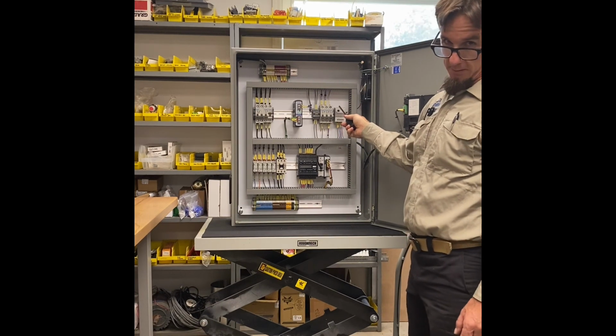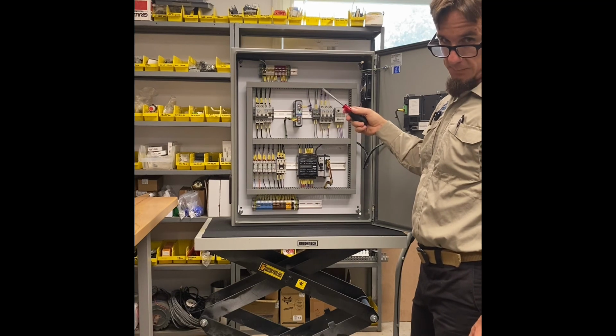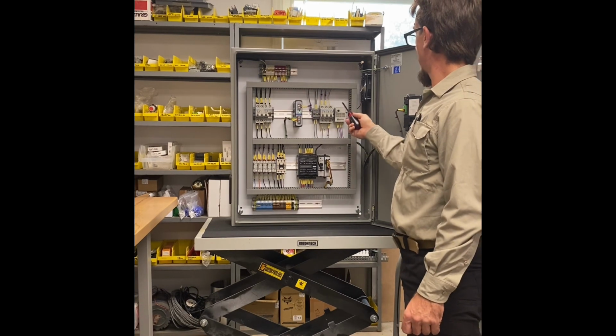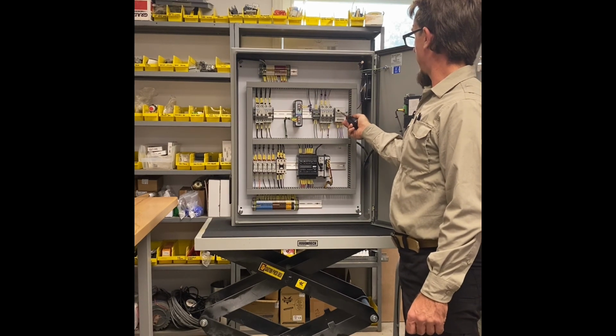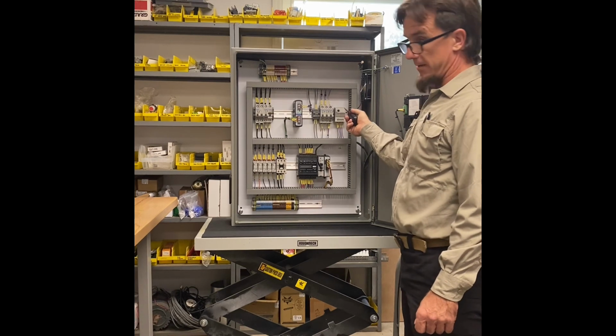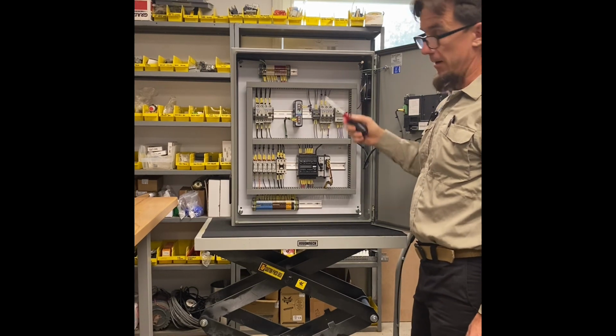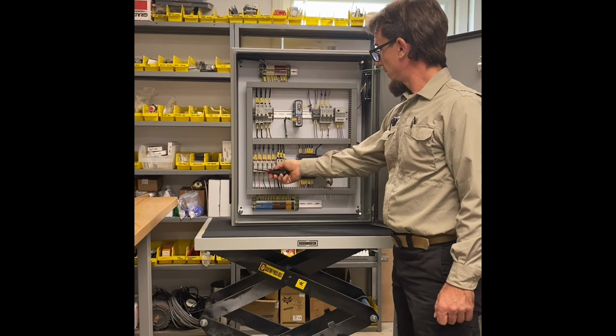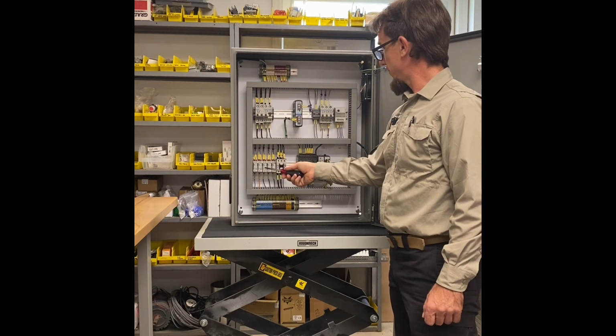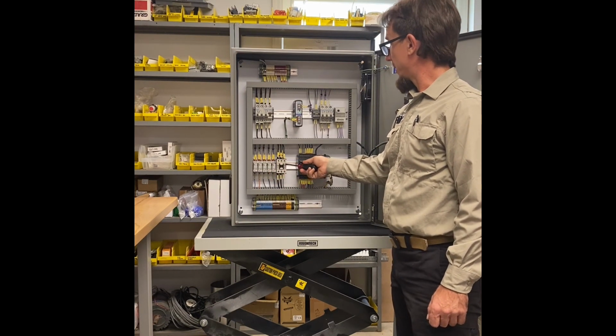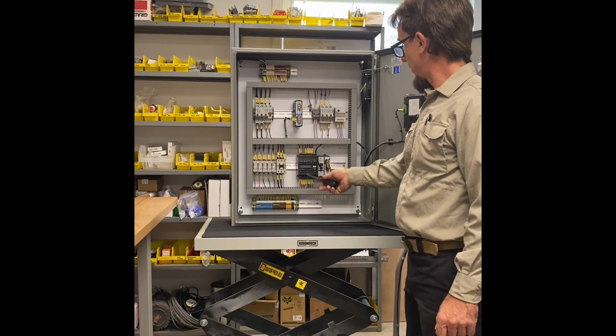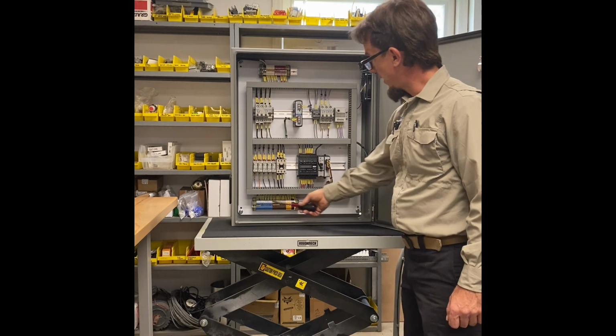I will not be turning the fan on for very long just because of the noise generation. To the right of the fan, we have the thermostat, which senses the temperature in the cabinet and turns the fan on and off accordingly. I have 5 relays here, 1 contactor for the booster pump, my programmable logic controller, and the terminal strips at the bottom.